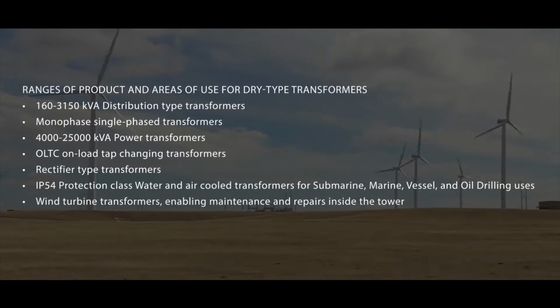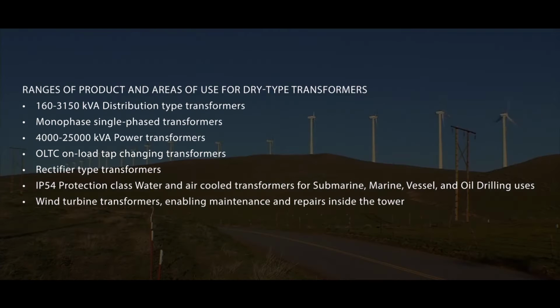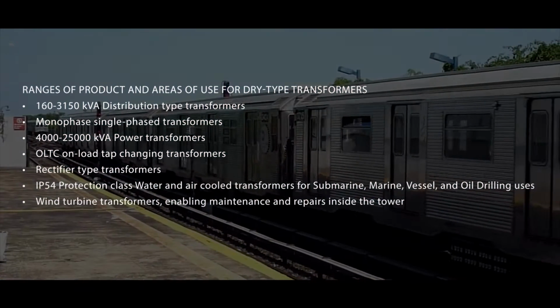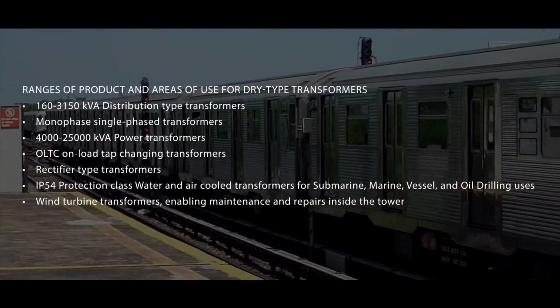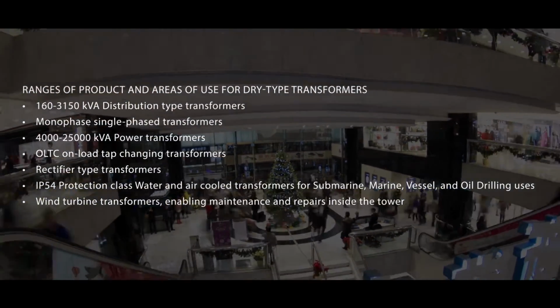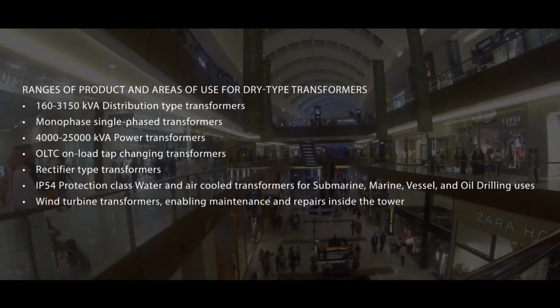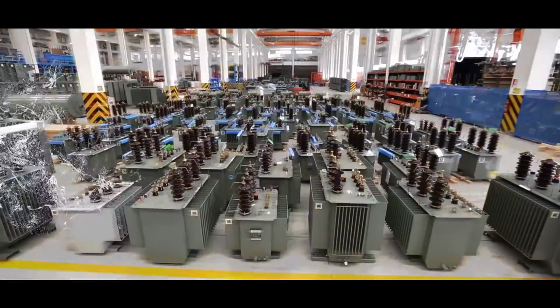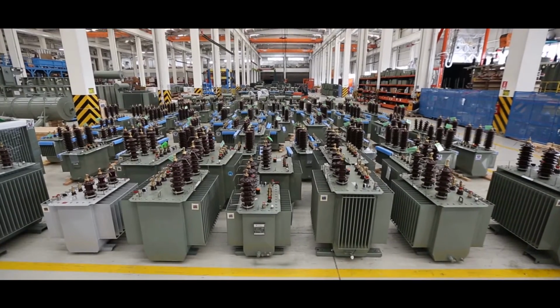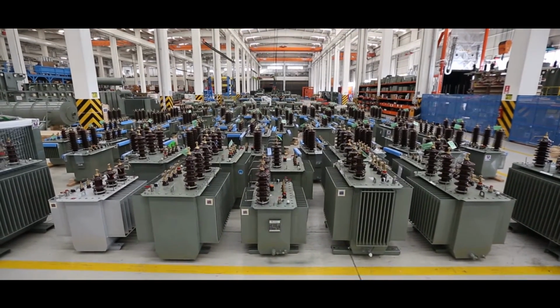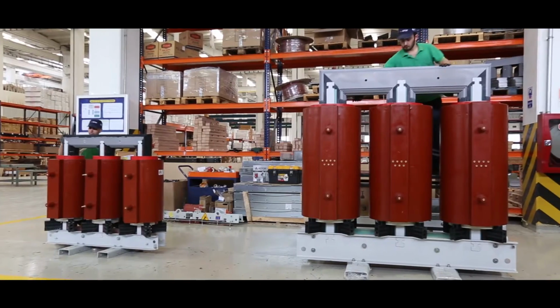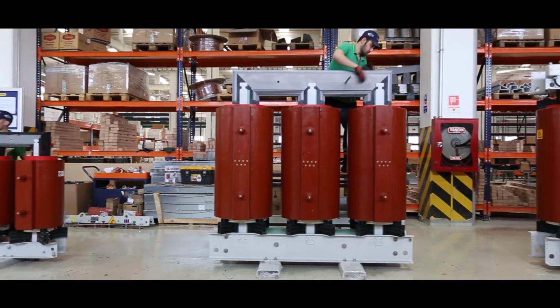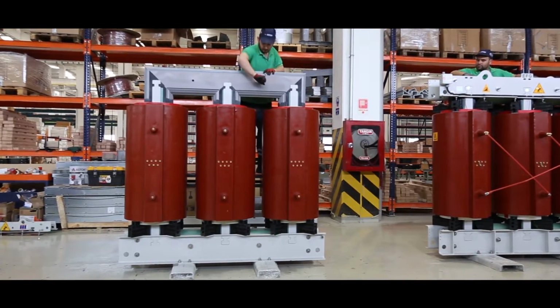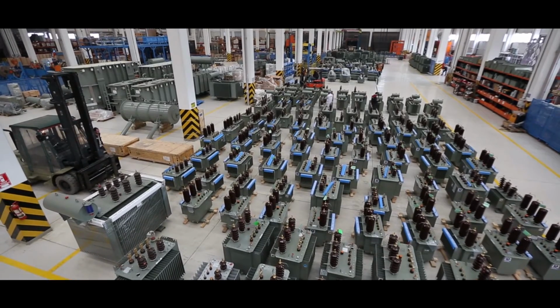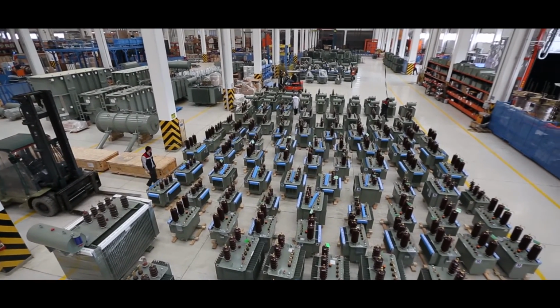air-cooled transformers for submarines, marine vessels and oil drilling uses, wind turbine transformers, enabling maintenance and repair inside the tower, minimizes the risk of burning and explosion at locations with a high density of human habitation, such as subways, tunnels, mines, airports, shopping malls, schools, hospitals and skyscrapers. May be manufactured with an internal or external type cell as optional in conformity with IP20, IP23, IP33 protection classes. Apart from the aforementioned, our overseas type test reports for the product series within the product range are constantly updated and have been certified by the international accreditation testing organizations such as KEMA, IPH and CESI.